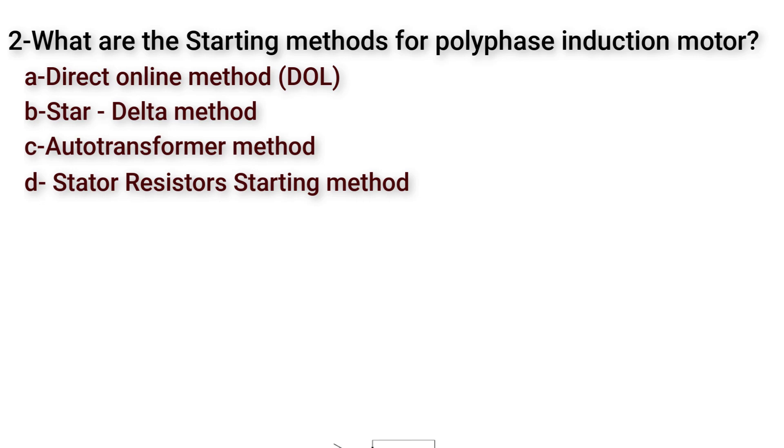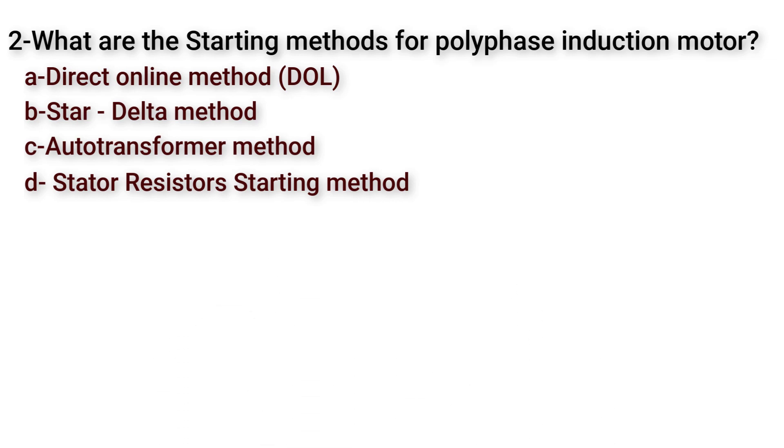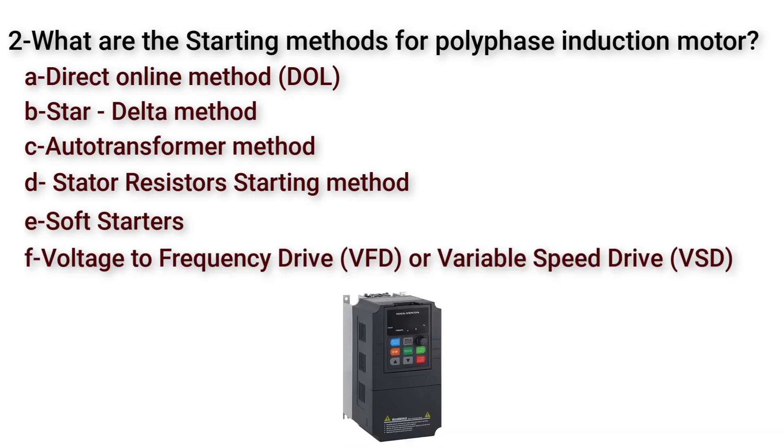Another method is stator resistor starting method. Here we connect resistors to stator windings to reduce the voltage applied on the stator. Then we will disconnect these resistors. Also we have soft starters which is an electronic device that reduces the voltage across the stator at starting. At last we have voltage to frequency drive or variable speed drive. Here we use electronic device which converts the three-phase applied voltage into DC. Then it will convert it again into three-phase AC variable voltage and variable frequency waveform.